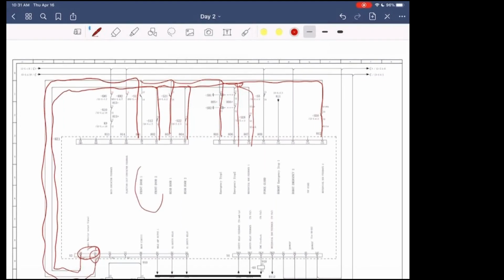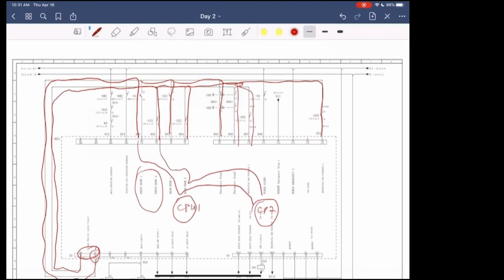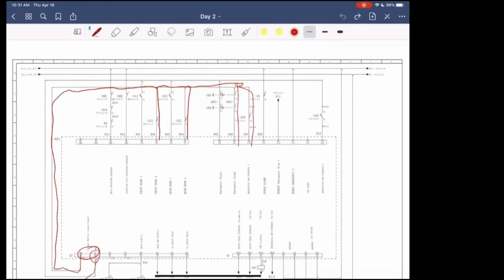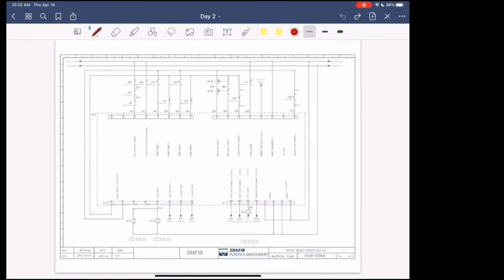So what it's looking for, for example, the front door has T0 and has a T1. So inside the safety unit, there's 2 CPUs. They're different CPUs. So you have CPU 1 and CPU 2. And what it does is it takes each one of these signals and goes to each one of the CPUs here. Each goes to here. And if they're both equal and they match, then you'll have an output. If you don't have a signal that matches what the signal is supposed to be, then you won't get an output, and your safety relay will go into an alarm. You'll have an I fault, and you'd have to open the door, reset whatever caused the input fault.